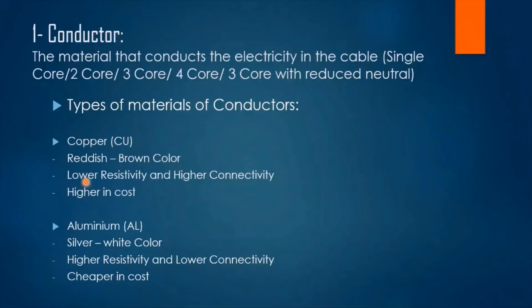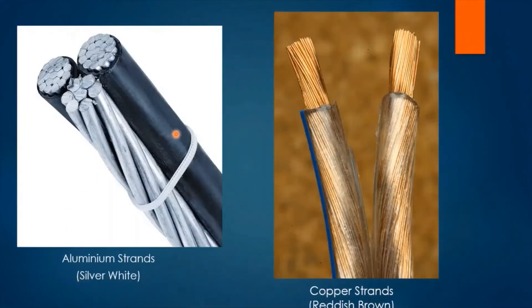On the other hand, if we want to select an aluminum cable, we would have to upgrade the size to 25 mm² to be able to withstand the 60-amp load. So the equivalence is: copper at 16 mm² equals aluminum at 25 mm², because copper has lower resistivity. Copper is also more expensive than aluminum, while aluminum is cheaper. This picture shows the color difference — aluminum has a silver-white color while copper has a reddish-brown color.